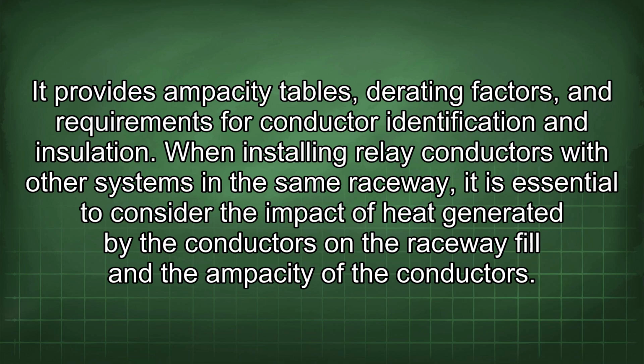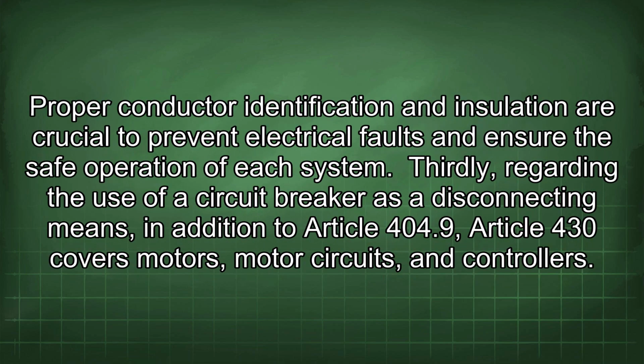When installing relay conductors with other systems in the same raceway, it is essential to consider the impact of heat generated by the conductors on the raceway fill and the ampacity of the conductors. Proper conductor identification and insulation are crucial to prevent electrical faults and ensure the safe operation of each system.